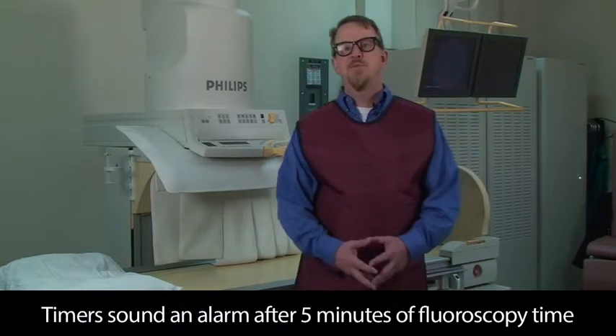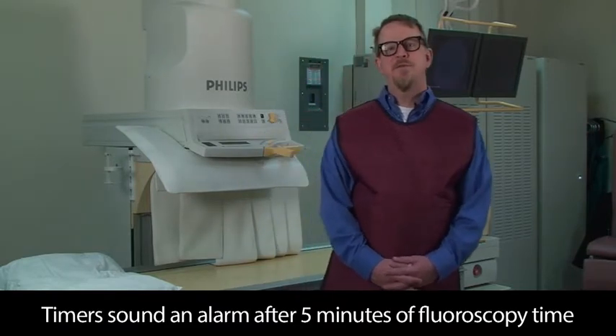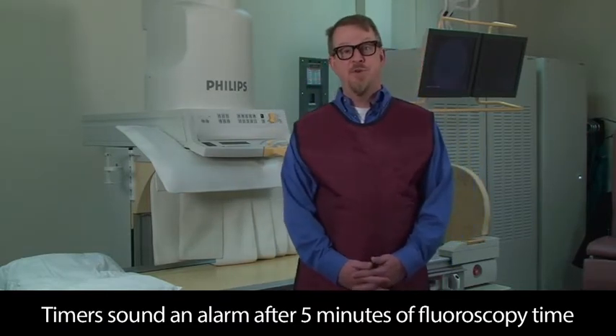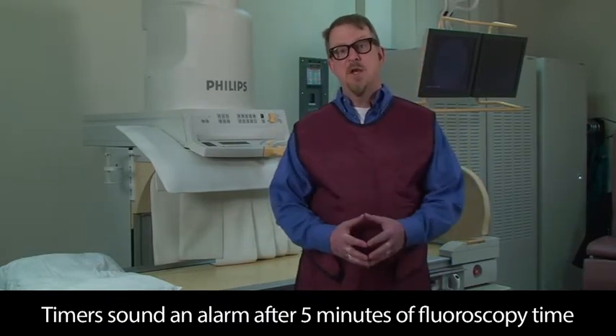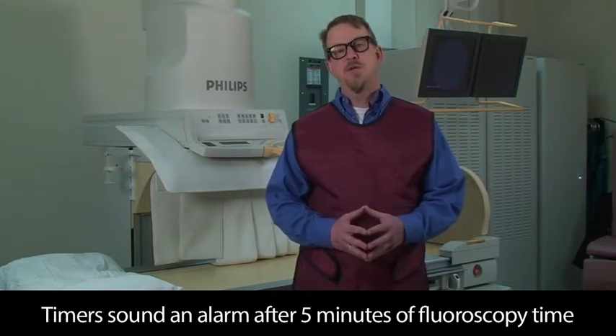Fluoroscopy units are equipped with timers that will sound an alarm after 5 minutes of fluoroscopy time, forcing the technologist or radiologist to acknowledge the cumulative exposure time and silence the alarm. Even before the alarm sounds, it is within the scope of practice for the technologist to remind the radiologist of exposure time for the safety of everyone in the room. Alarms will continue to sound at each 5-minute interval of fluoroscopy time.